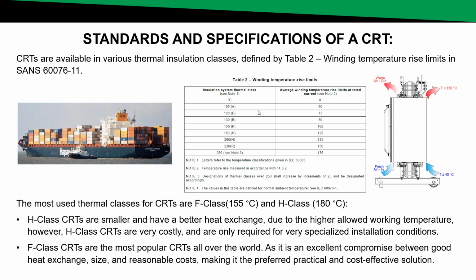H class transformers are smaller and have a better heat exchange rate due to the higher temperature allowed for the insulation. These transformers are, however, very costly, and the insulation material is very expensive, and this type of H-class transformer is usually only required for very specialized installations. The most commonly used cast resin transformer in the world is the F-class. This is an excellent compromise between good heat exchange, size, and reasonable cost, making it the preferred practical and cost-effective solution for cast resin transformers.